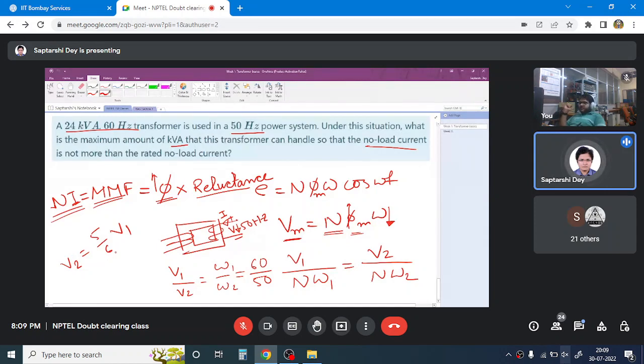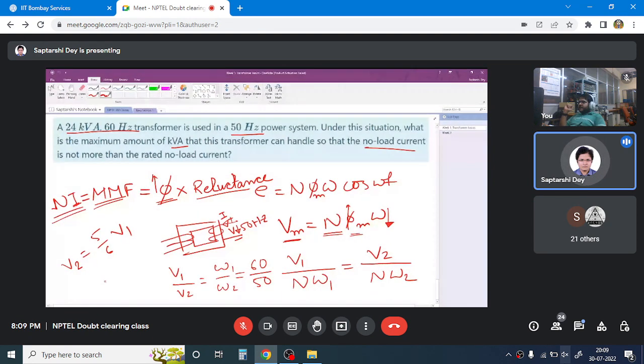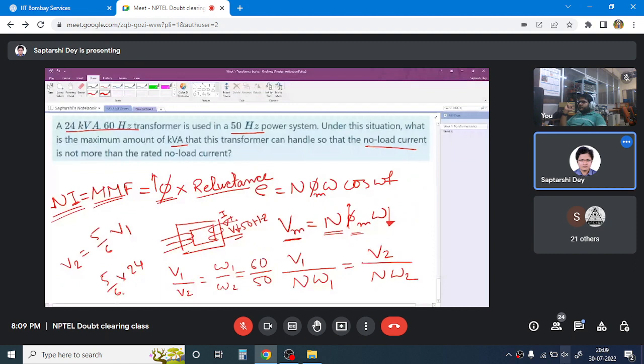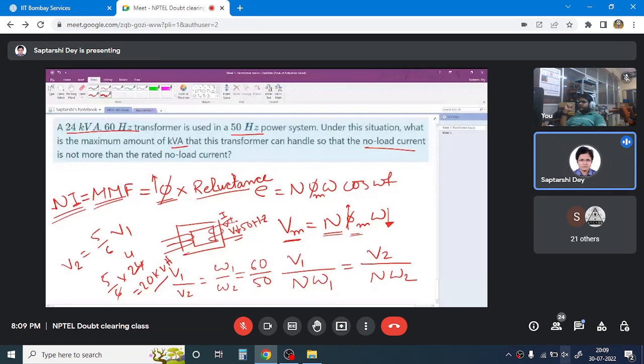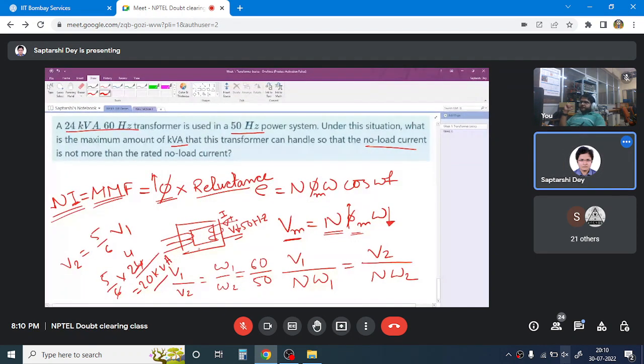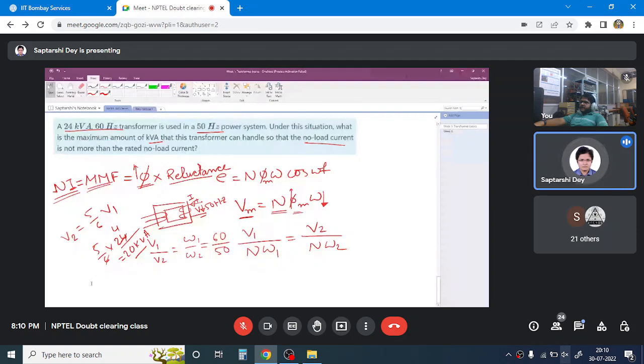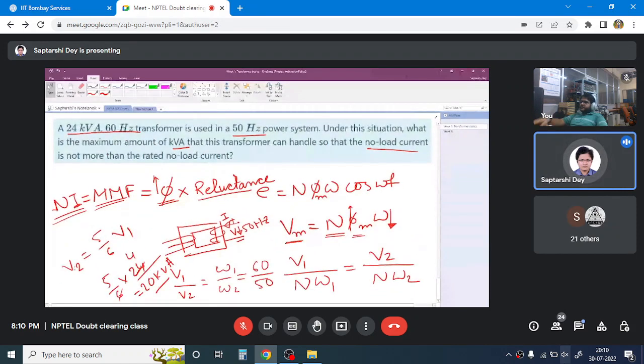So if my voltage is reduced by this factor and my current is kept constant, my kVA rating will also be reduced by this factor, isn't it? It was 24 initially. It becomes 5 into 4, 20 kVA. So this is the rating. I cannot exceed this much volt ampere rating. You see, we are again coming back to that question, why is a transformer rated in kVA?